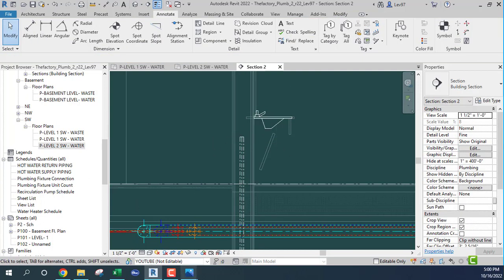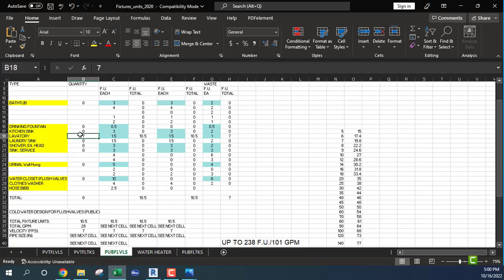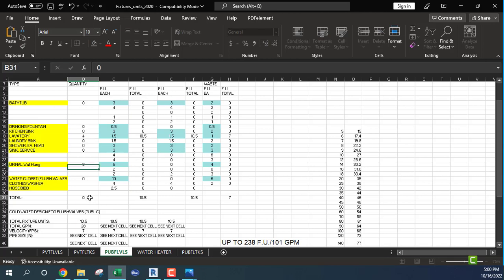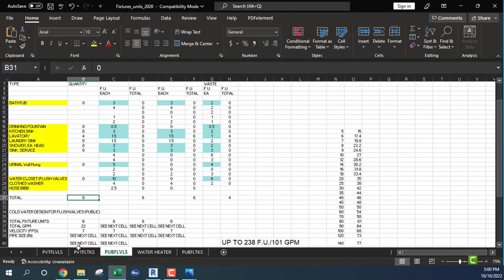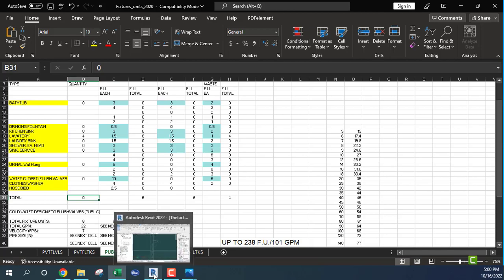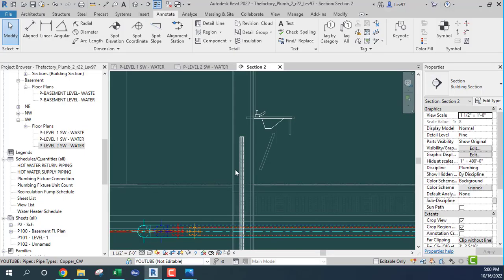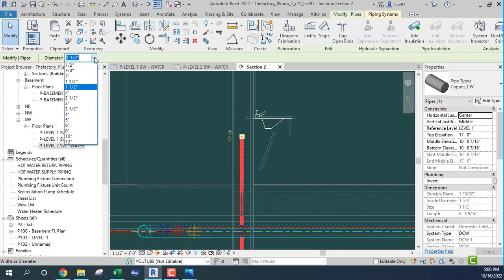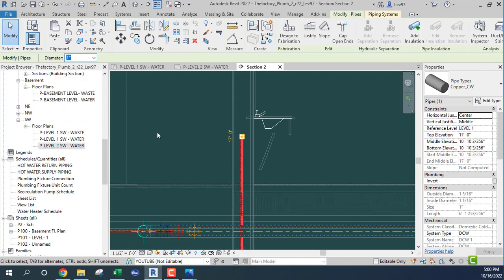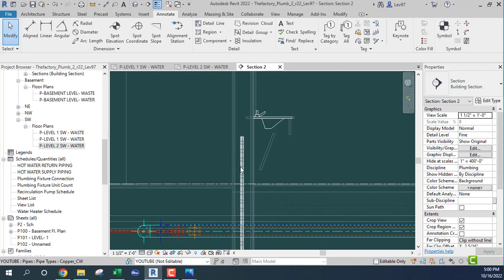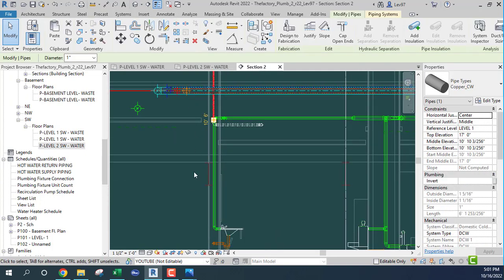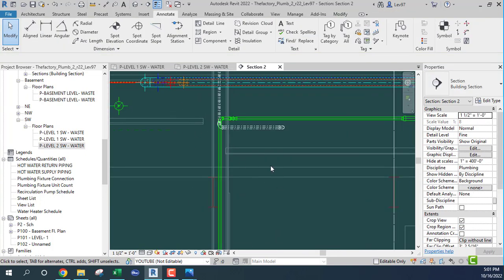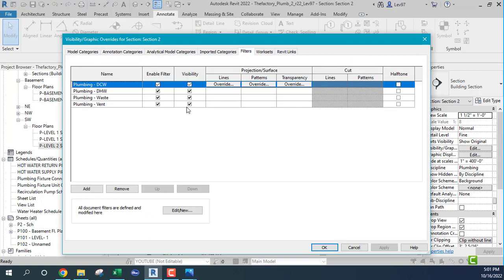This is going to be a different size. There are four lavs going to the second level, which comes out to about 22 GPM. You can kind of eyeball it at this point — I would change this to a one inch. Turn off the vent using VV.